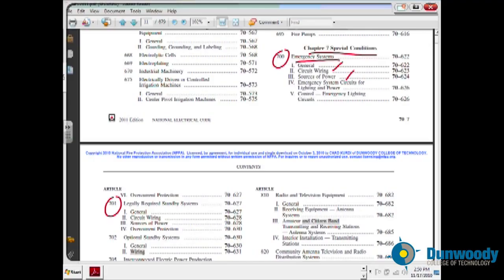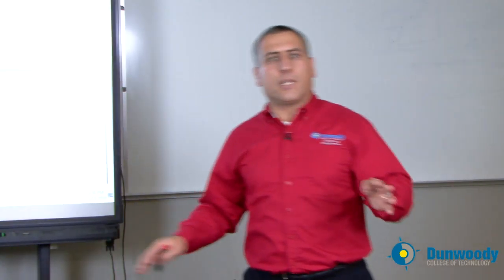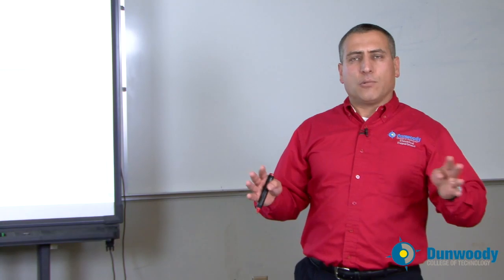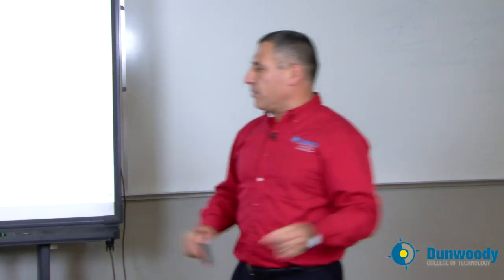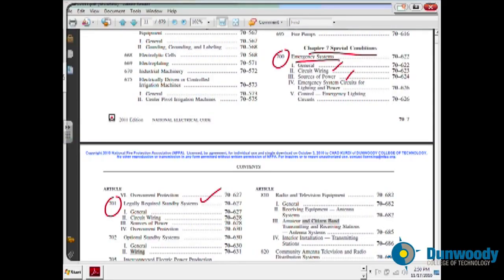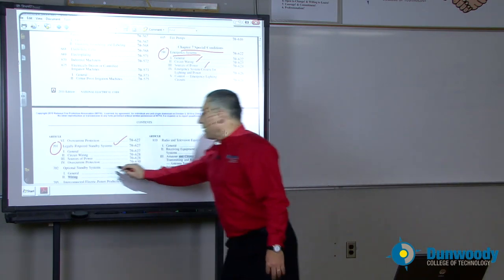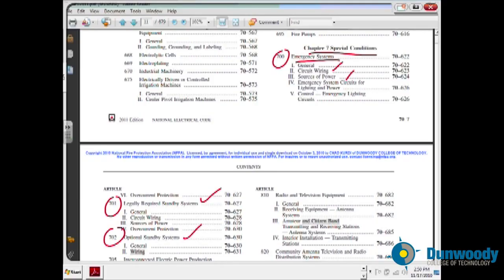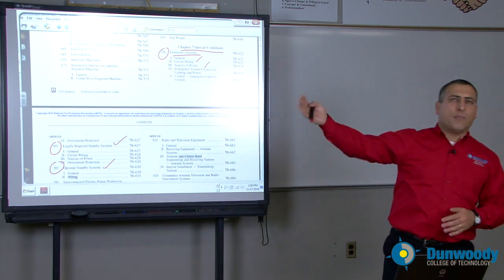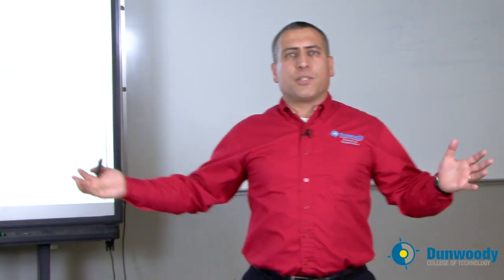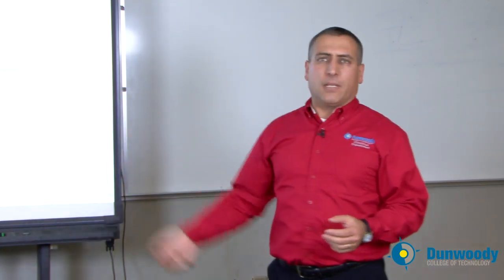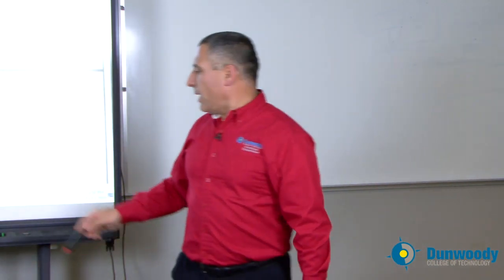There is another system called the legally required system, where the authority having jurisdiction — state government, local government, or federal government — requires certain buildings to have a backup system in case of emergency. You're going to find this information in the legally required system. Optional system: if we here at Dunwoody decided to back up our building with two MEC generators, that would be an optional system. It's not required by a government, it's not required by the building code.